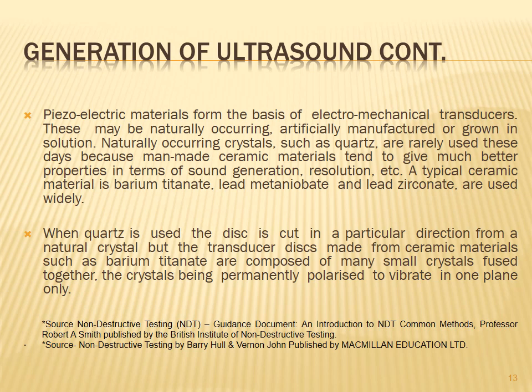When an alternating voltage is applied across the thickness of a disk of piezoelectric material, the disk will contract and expand, as shown in slide number 12. This is the principle of how compressive waves are generated. In doing so, a compressive wave normal to the disk in the surrounding medium is generated.